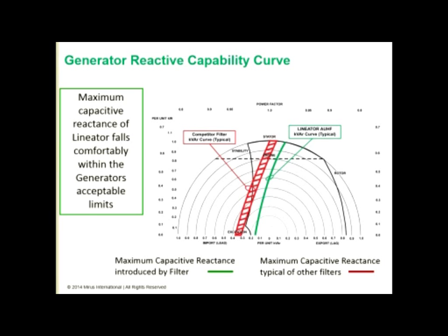The typical reactive power curve of most other filters is shown in red. At lighter loads, the capacitive reactance exceeds the acceptable levels of the generator and is therefore likely to cause compatibility issues such as excitation control or regulatory problems.